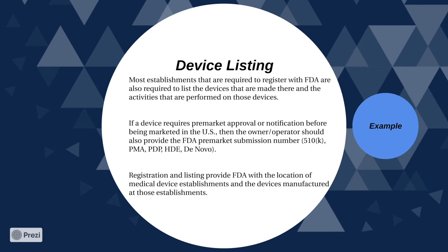Moving on to device listing: most establishments required to register with FDA are also required to list the devices made there and the activities performed on those devices. If a device requires pre-market approval or notification before being marketed in the US, the owner or operator must also provide the FDA pre-market submission number. Registration and listing provides FDA with the location of medical device establishments and the devices manufactured there.